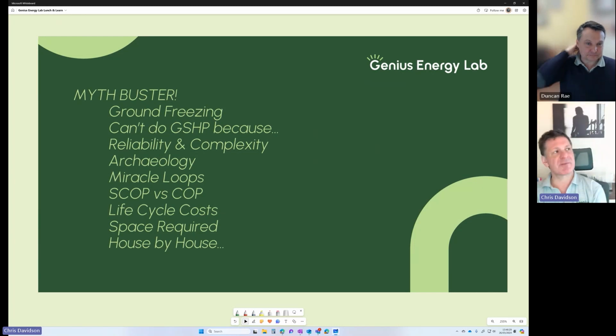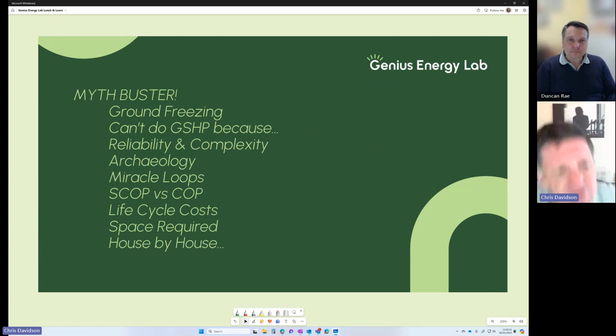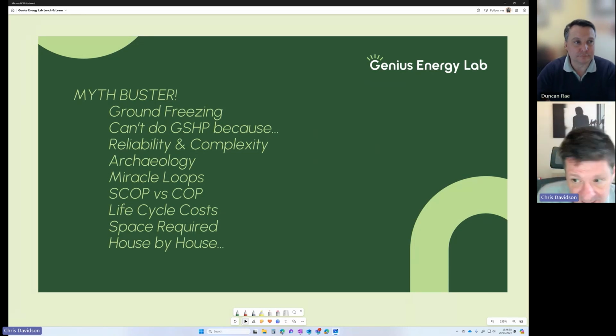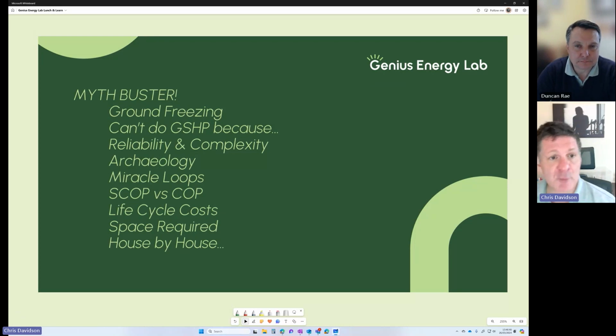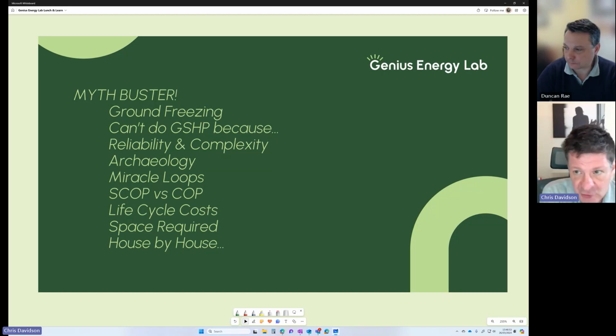All right, myths. There are plenty of myths around ground source, and so let's bust a few of those. People often talk about the ground freezing. We do run at negative temperatures in ground loops, and there's nothing wrong with that. But if you are seeing adverse effects at the surface or in structures as a result of that, then you've just got a badly designed and inadequately designed ground loop. So we don't freeze the ground. We do run at negative temperatures in ground loops. And as I say, there's nothing wrong with that. So let's deal with that one.